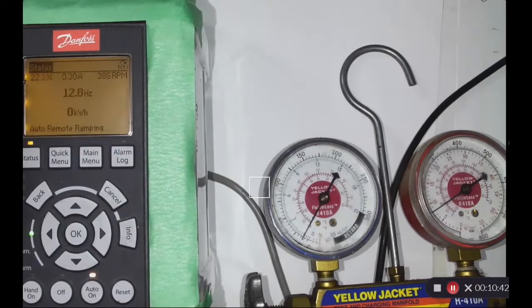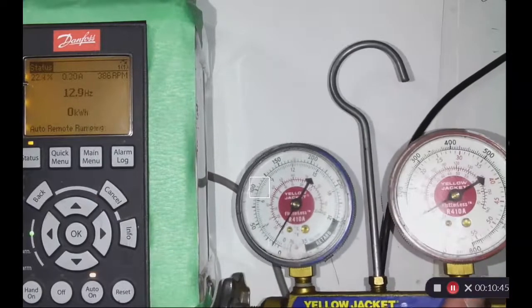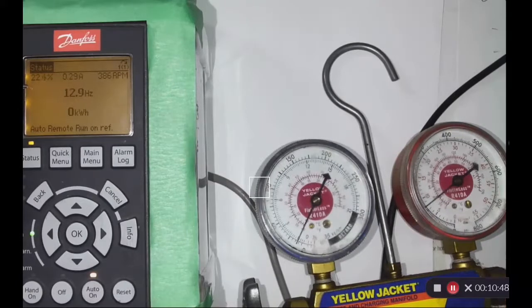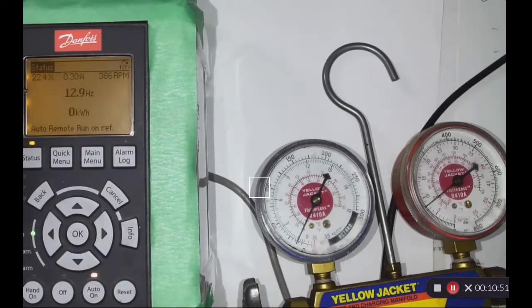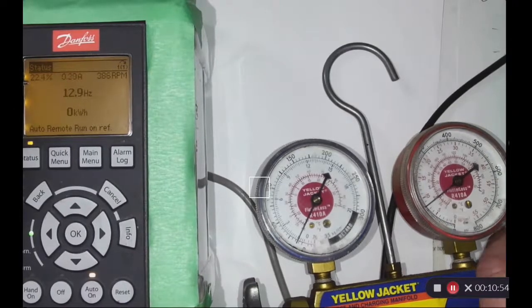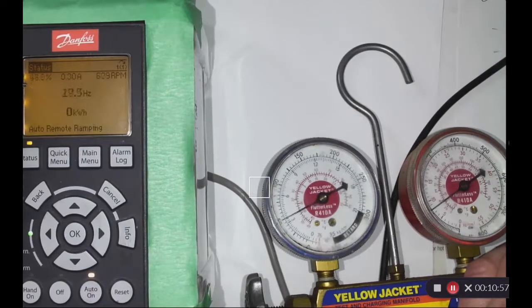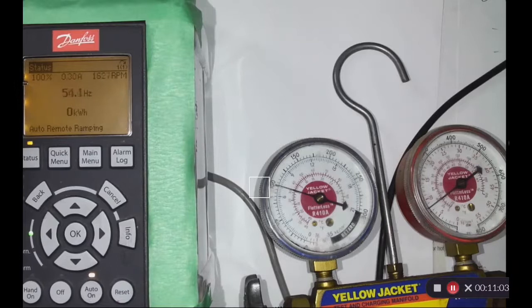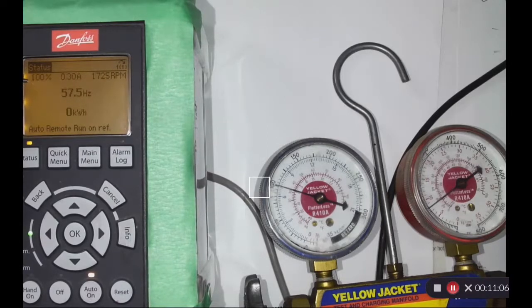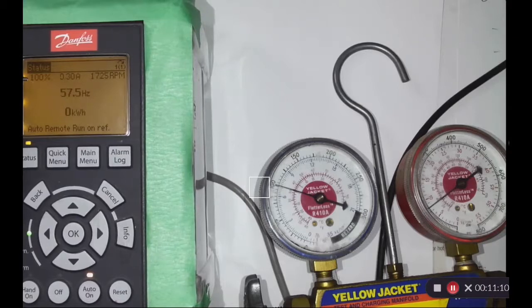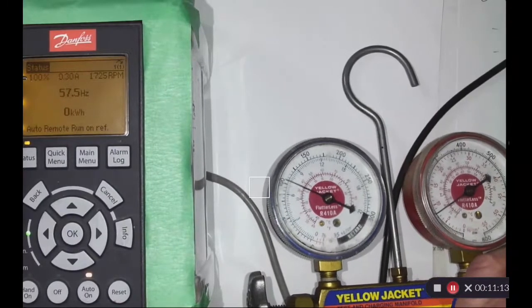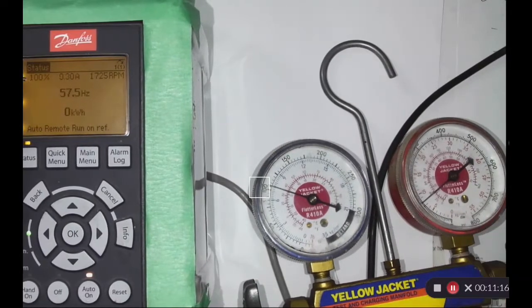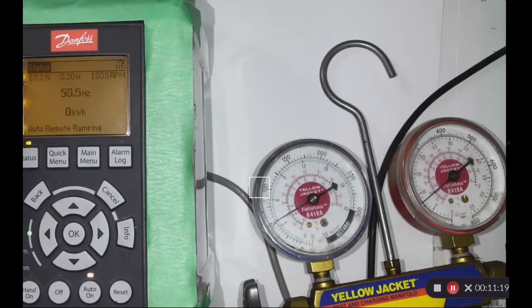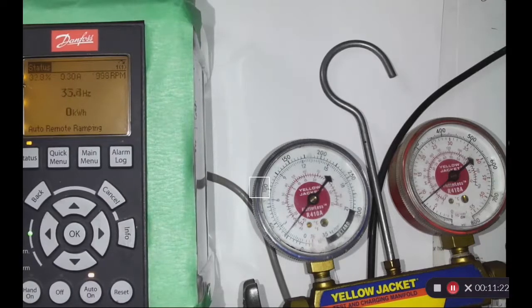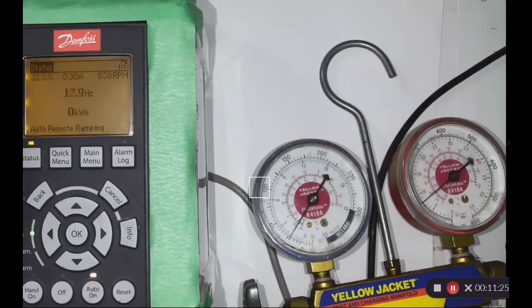There, I'm at, looks like, I'm going to say somewhere around maybe 10, 15 pounds of pressure. So we're still not down at the low end of the scale, but you get the idea. You want it to go faster, then we watch the head pressure would climb because the fans aren't on, and the fans eventually come on, and it brings my fan motor to the maximum RPM, trying to maintain X amount of pounds of head pressure. When I bleed the pressure off, he says with a grin, pressure's going to fall, so does my output from my transducer, and eventually it goes down to the minimum 10 hertz.